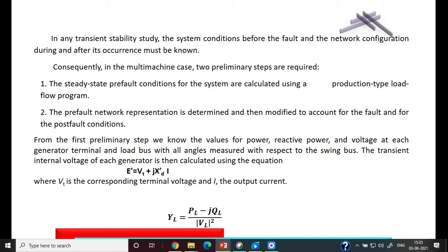For the multi-machine case, two preliminary steps are required. First, steady-state pre-fault conditions are calculated using a load flow program. Second, the pre-fault network representation is determined and then modified to account for the fault and for the post-fault condition.